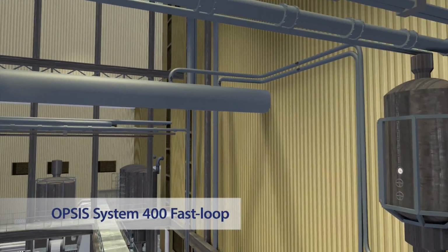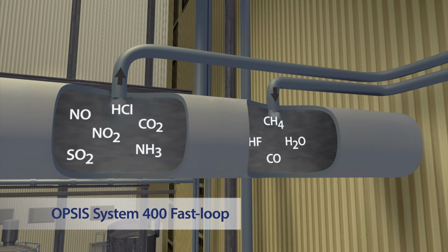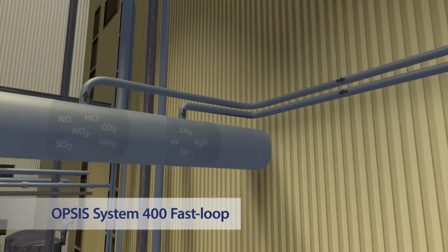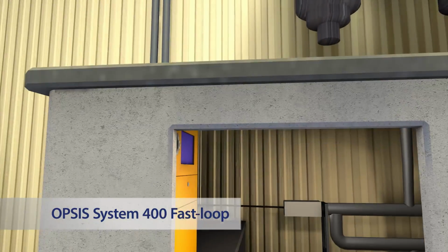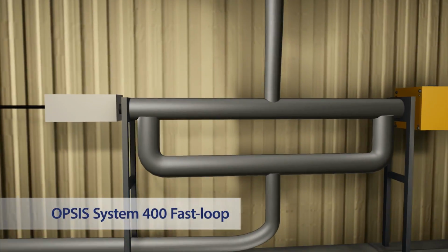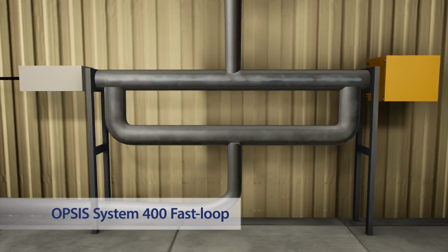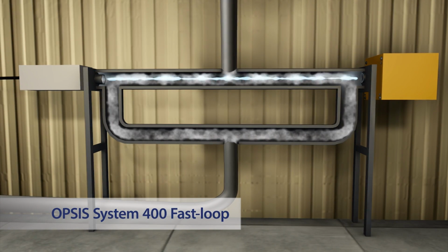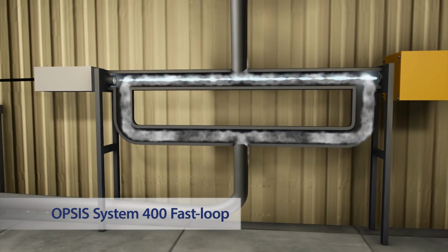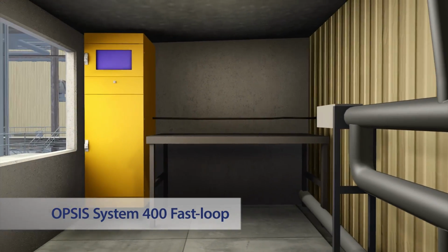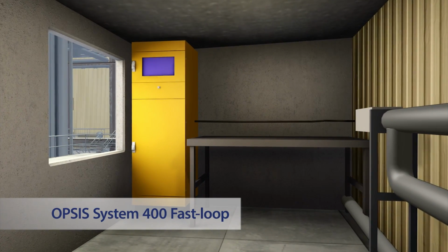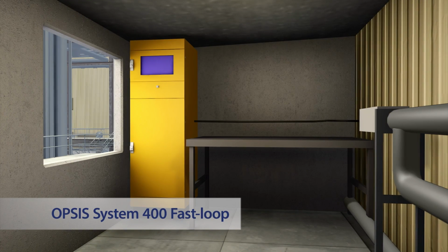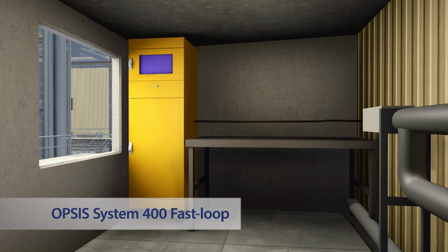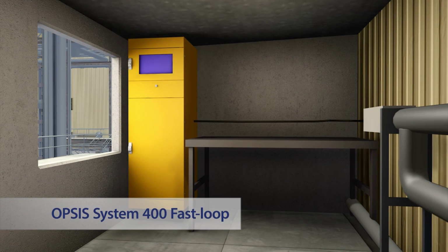With OPSIS System 400 Fast Loop, the flue gas is moved at high speed via a heated bypass line to the measurement cell with the aid of a fan. In the measurement cell, the gas is measured using the OPSIS DOAS technique. The receiver is connected to the analyzer using fiber optic cable. A single OPSIS System 400 Fast Loop measures all relevant gas emissions in the same way as the cross-stack. However, the fast loop is the best solution when the measurement point is difficult to access.